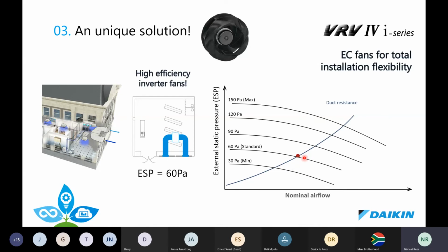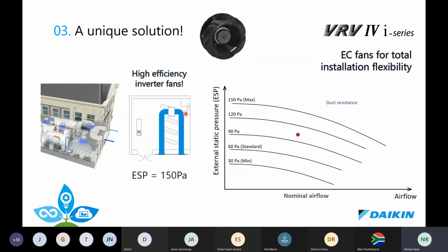External static, you're looking at about 60 pascals standard. That should be more than enough to duct your air out, even with a dirty filter, and you can go to a maximum of 150 pascals. So let's say, for example, this is where your storeroom was, and you wanted this unit to be housed there because of maintenance and not to interfere in the normal working operation of your offices. You could increase that, and your consultant or your contractor will have to calculate that 150 pascal duct run to draw the air out.